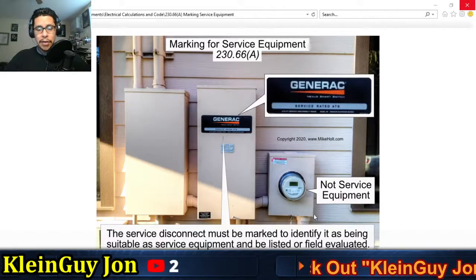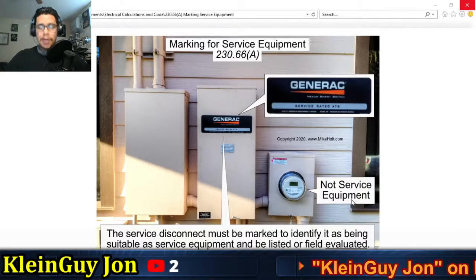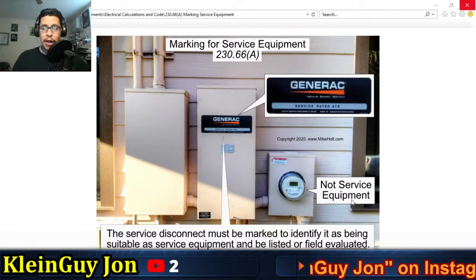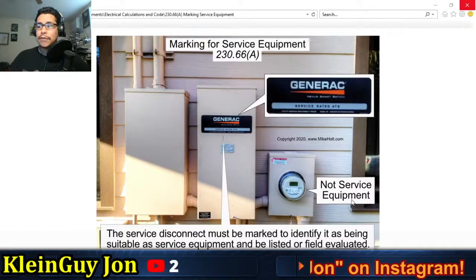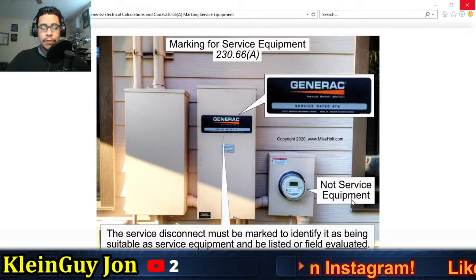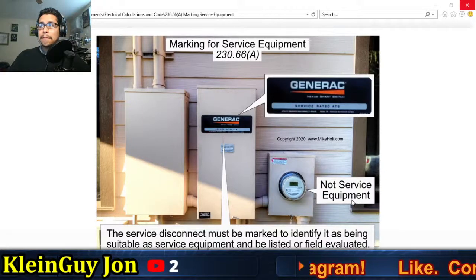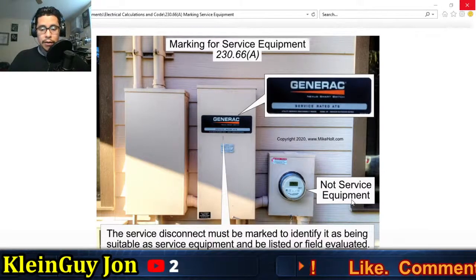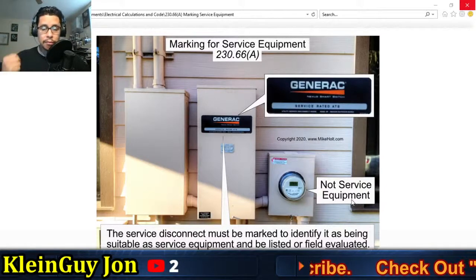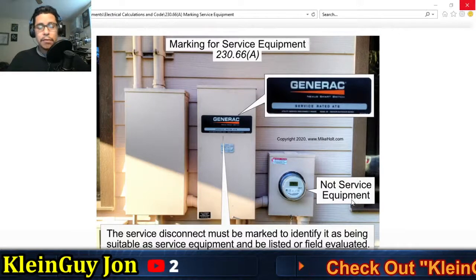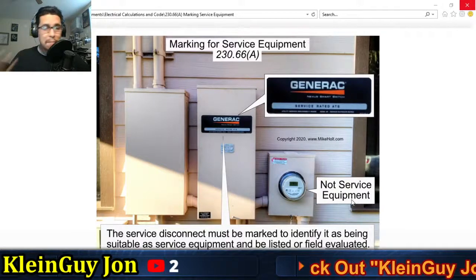The meter is not service equipment. A lot of confusion on that as well, I hear a lot of that, and I'm going to have to say I totally agree with this article. A meter is not considered service equipment. You can't just go in there and disconnect the meter. Meters are mostly locked, for reasons, for the utility. The meter is part of the utility company that is metering your consumption of power.